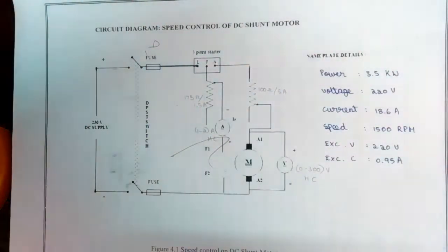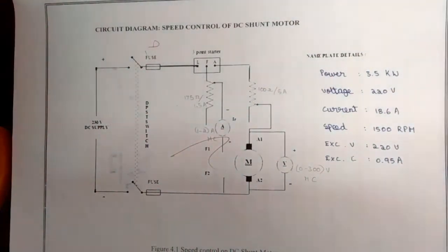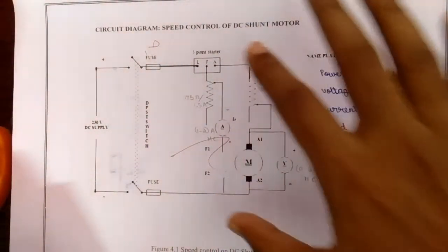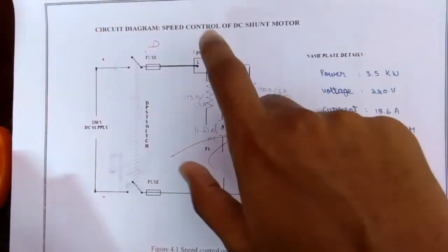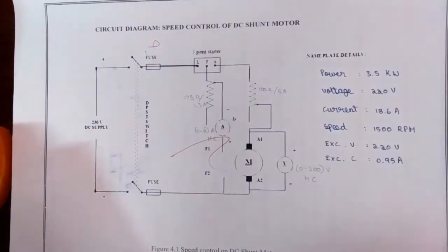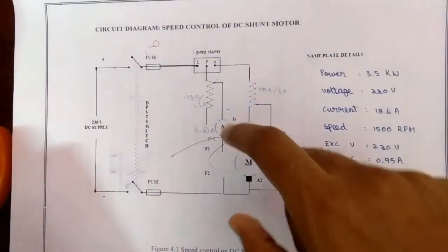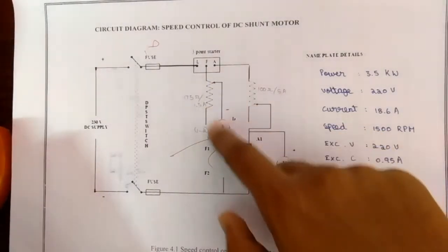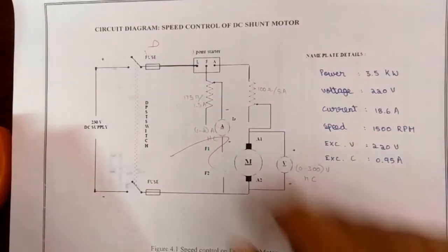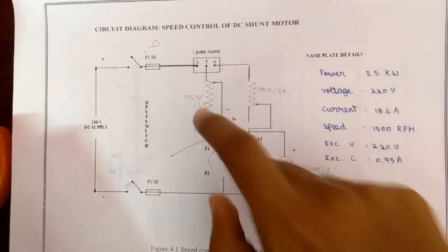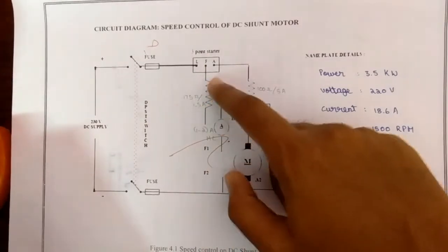For the armature control method, the procedure is: again the DPST switch is closed and the motor is started using the three-point starter. The armature is connected in series with the armature rheostat. With this field rheostat the field current IF is maintained at a constant value by adjusting the field rheostat.